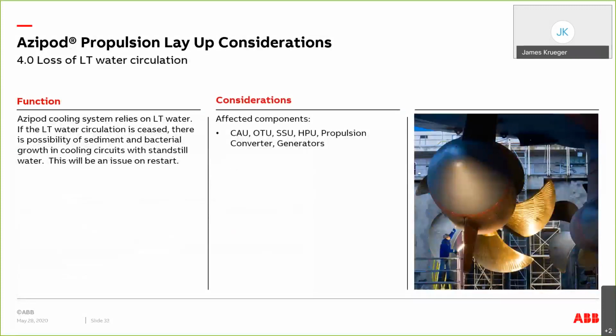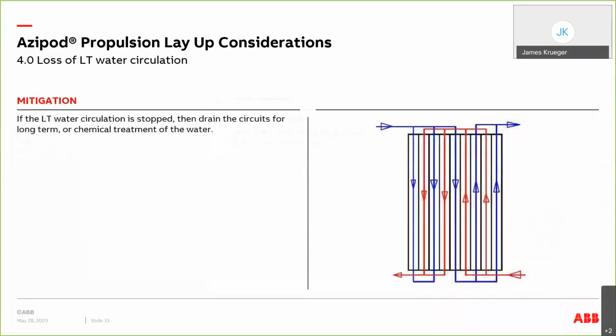I think Teemu mentioned a little bit about the loss of LT water. So the low temperature water circulation is important in the AZIPod for cooling of certain components, including oil temperature or oil lubrication systems and those type of systems. The concern is that if the LT water circulation is shut down and there's still water in the system, then bacterial growth will quickly ensue and/or sediment can happen. And unfortunately, the small areas within the heat exchangers can get plugged, and that will be an issue on the restart.